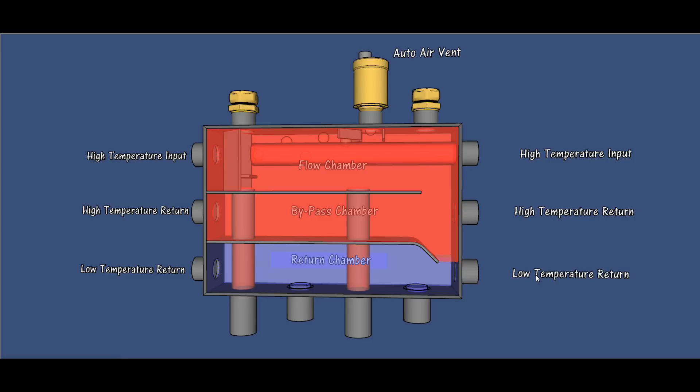You could have a high temperature return, say for instance on the left, and a low temperature return to a different boiler on the right. Or vice versa - a low temperature boiler on the left hand side with the return taken from the bottom chamber.